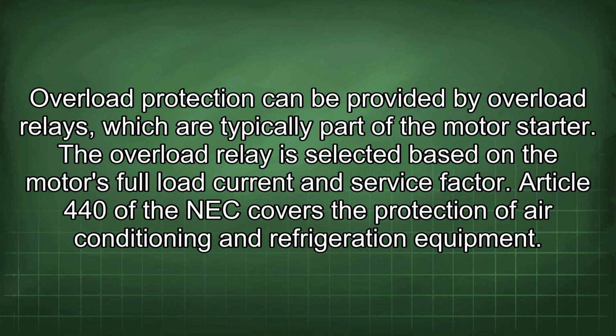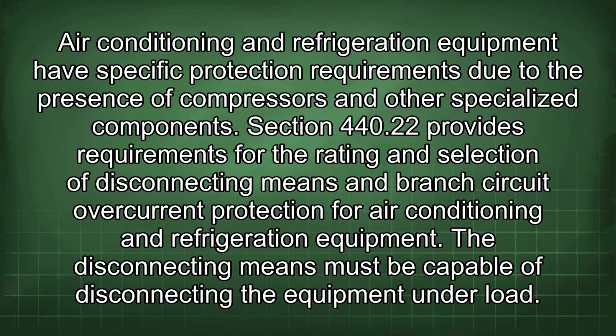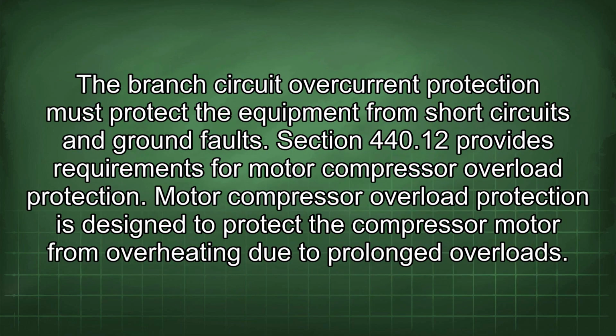Article 440 of the NEC covers the protection of air conditioning and refrigeration equipment. Air conditioning and refrigeration equipment have specific protection requirements due to the presence of compressors and other specialized components. Section 440.22 provides requirements for the rating and selection of disconnecting means and branch circuit overcurrent protection for air conditioning and refrigeration equipment. The disconnecting means must be capable of disconnecting the equipment under load. The branch circuit overcurrent protection must protect the equipment from short circuits and ground faults.